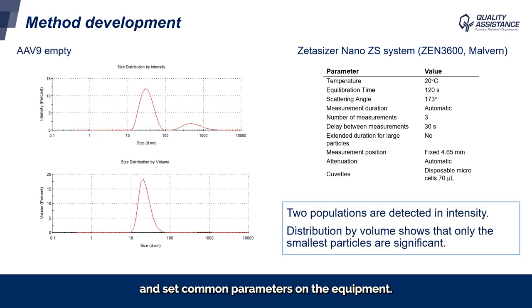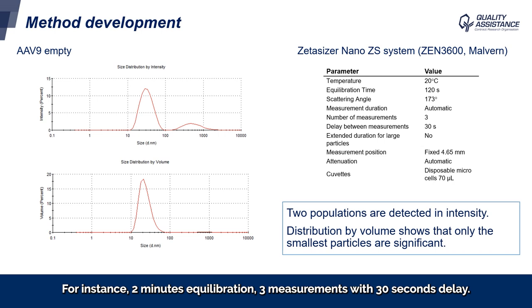We currently have three Zetasizer instruments available at Quality Assistance, and one in particular is dedicated to AAV analysis in a biosafety level 2 environment. Although this approach will not be presented today, one of the instruments can also perform measurements in multi-angle mode, which provides information on particle concentration in addition to size. For method development purposes, we used an empty AAV9 sample and set common parameters on the equipment — for instance, two-minute equilibration and three measurements with 30 seconds delay.